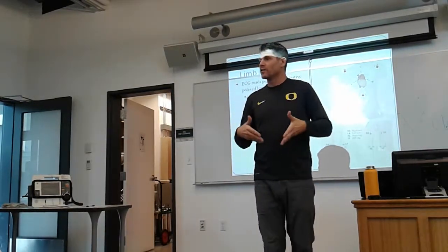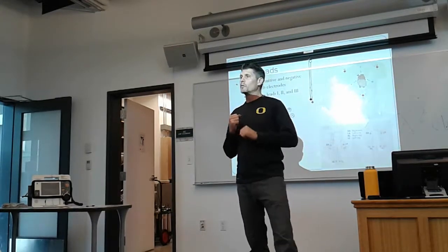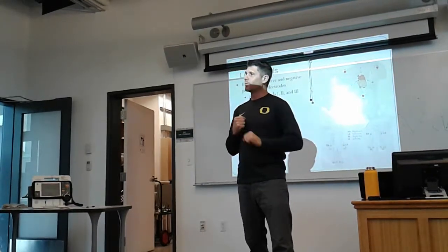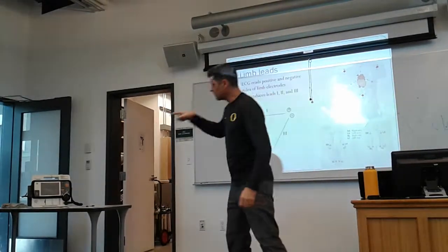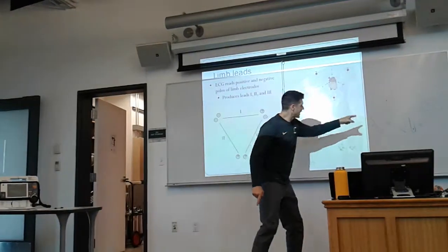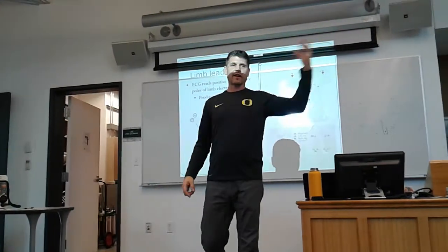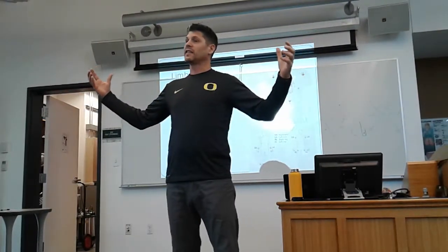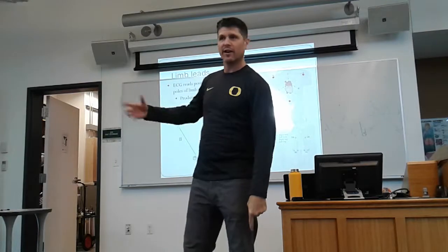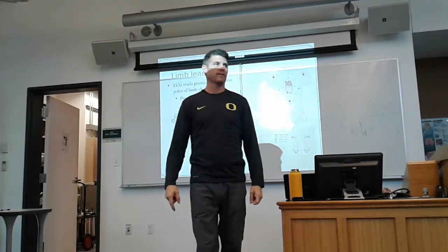There's multiple wires inside the cable that's going to that leg. Some of those wires can be positive, some can be negative, and some can be a ground. And so this machine does that exact thing. When you want to see lead 1, then it puts the positive here, the negative here, and the ground on the leg. If you want to see lead 2, then it puts the positive there, the negative here, and it puts the ground up here, and it automatically makes that shift.